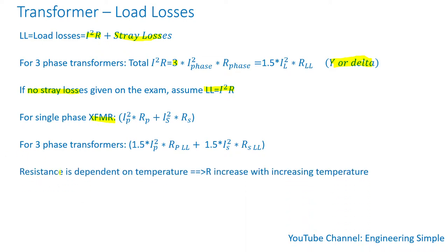One thing to keep in mind is that resistance is dependent on temperature. As temperature increases, resistance increases. Typically when load losses are measured, they are measured at ambient temperature and then converted to a reference temperature per IEEE or per spec.